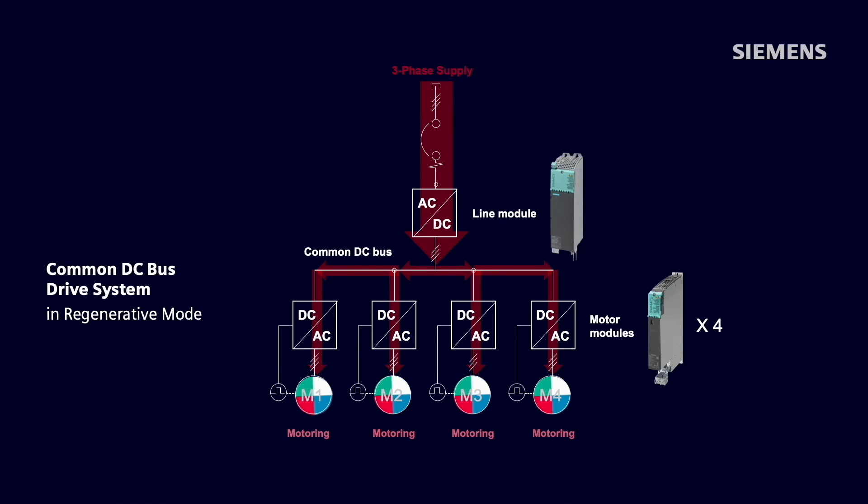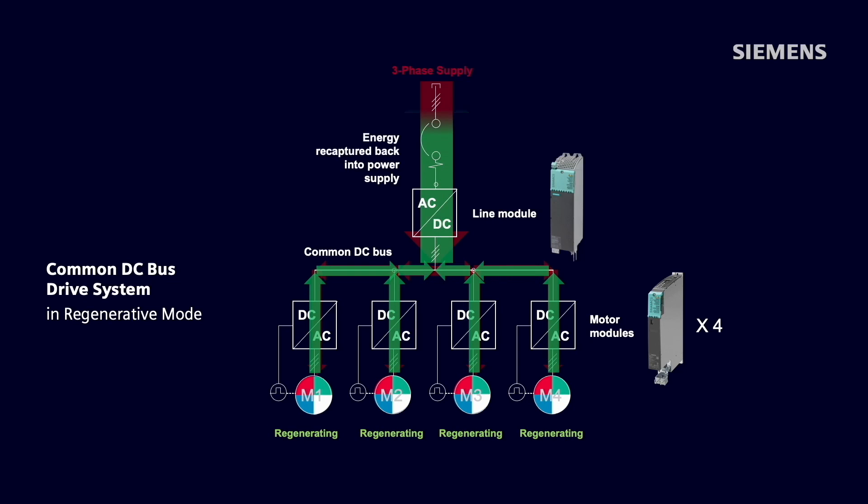Let's also take a look at a machine that has multiple cycles where energy would be regenerating from all axes at the same time. Instead of this power being dissipated across a braking resistor, it makes more sense to recapture this energy back into the power supply. This is where a regenerative line module such as a smart line module or active line module really shine. This not only saves money on power bills, but can also create a very green solution for many applications where a good amount of dynamic load cycle is available for energy recovery.